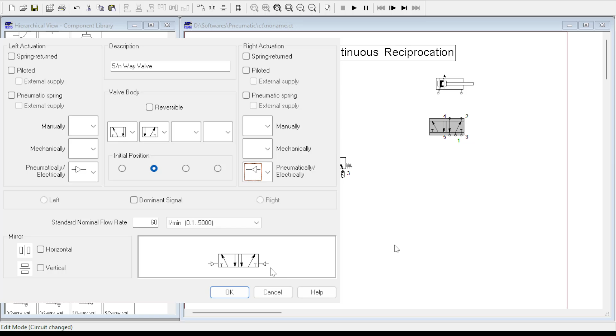Similarly, let us configure the cylinder for labeling the retracted and extended position of the cylinder. One thing to be noted in the simulation environment is that the same labels should not be used for different elements. So let us use a different label here for the double acting cylinder. Let us give a name like A0, which is another convention of labeling. Let A0 denote the retracted position, which will start at 0 position of the stroke length. And let A1 denote the extended position, which will be covering the complete stroke length of the double acting cylinder, which in this case is up to 100 mm.